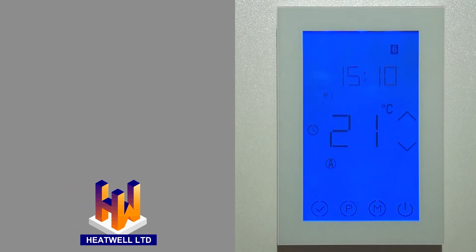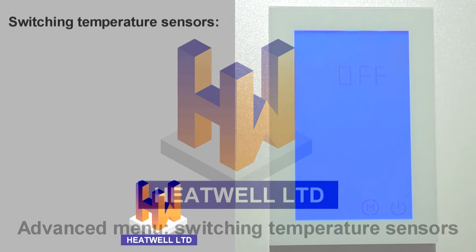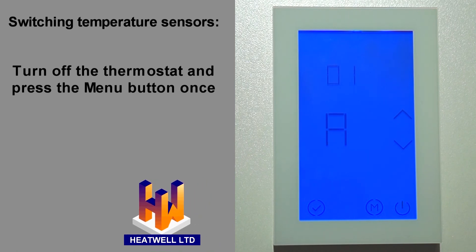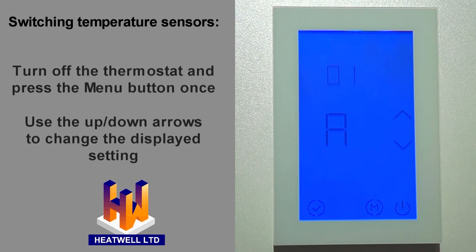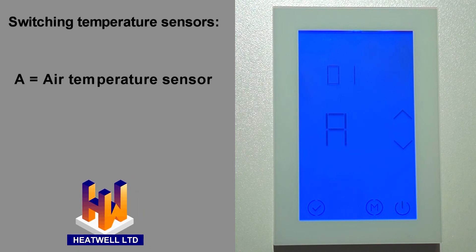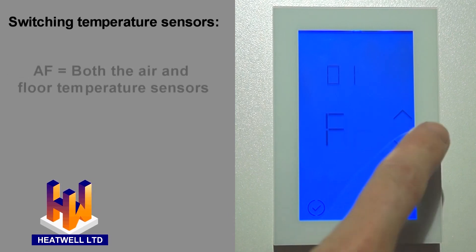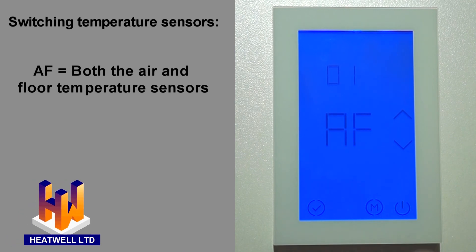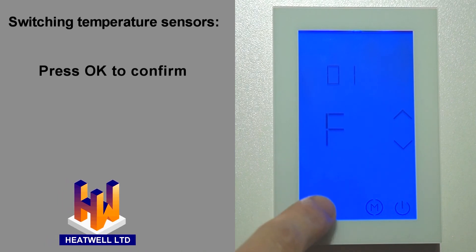Let's move on to advanced settings, starting with switching between temperature sensors. With the thermostat off, access the advanced settings menu by pressing the mode or menu button. Menu number 1 will be displayed, along with the chosen thermometer setting, which you can change by using the up and down arrows. A means the unit will use its air temperature sensor. F means the unit will use the floor temperature sensor. AF means the unit will use both the air and floor temperature sensors together. In this instance, we'll select F for floor. When you've made your selection, press the OK button to save and exit.